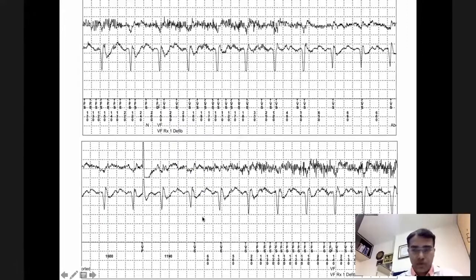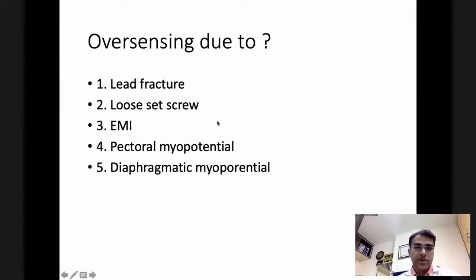So if we go back to the options one by one, in lead fracture, generally this kind of uniform nature of electrogram and noise is not visible. Generally lead fracture and loose set screw have a make and break kind of signal. Usually you have sometimes a high signal with a saturation with cutting of the electrogram. Almost the whole of your printing screen will be having that. Both lead fracture and loose set screw also will have some kind of impedance changes, although I have not given the data. EMI, as I discussed, can affect the far field as well as near field.